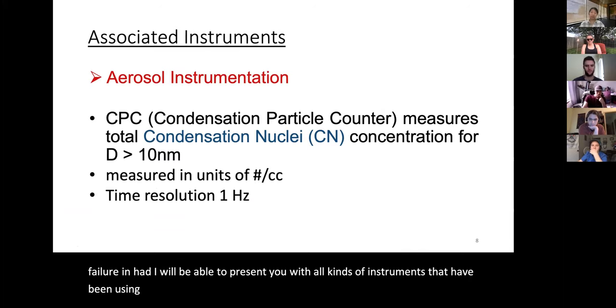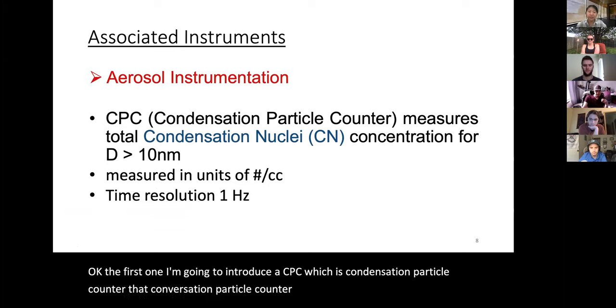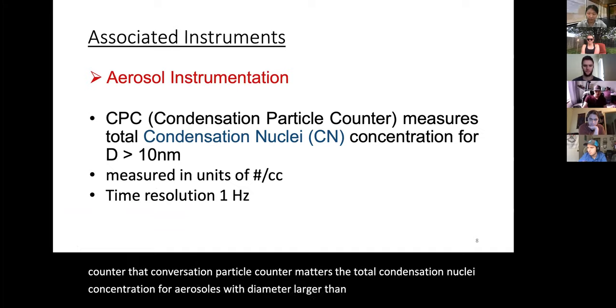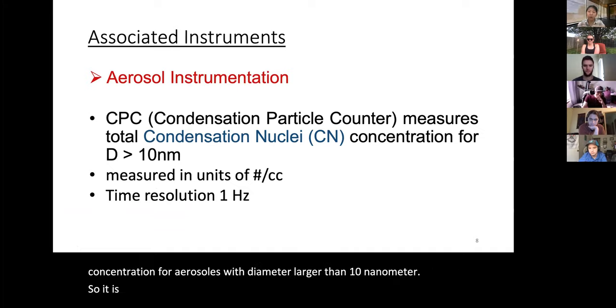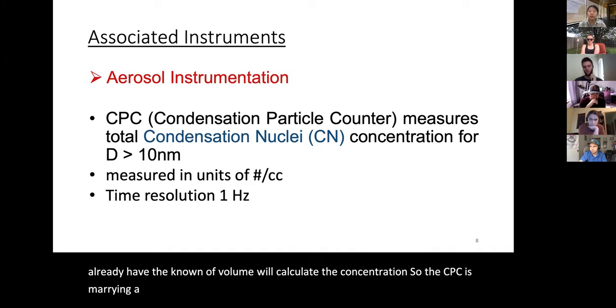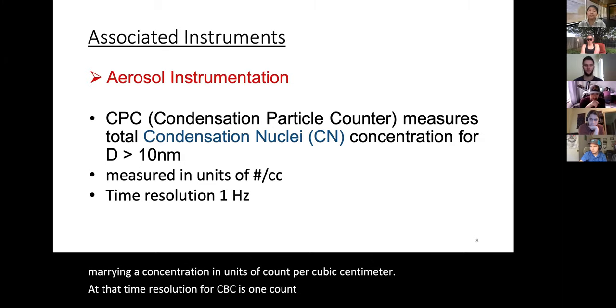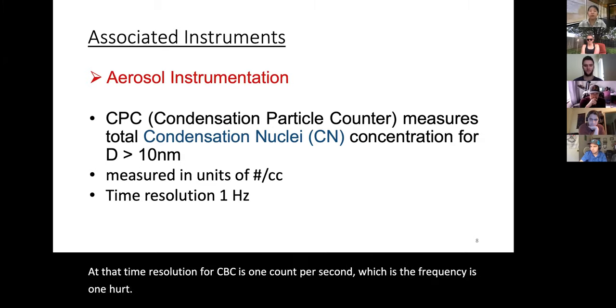The first instrument is the CPC — the Condensation Particle Counter — which measures total condensation nuclei concentration for aerosols with a diameter larger than 10 nanometers. It counts the total particle number collected within a known volume and calculates concentration in units of count per cubic centimeter. The time resolution for the CPC is one count per second, or a frequency of 1 Hz.